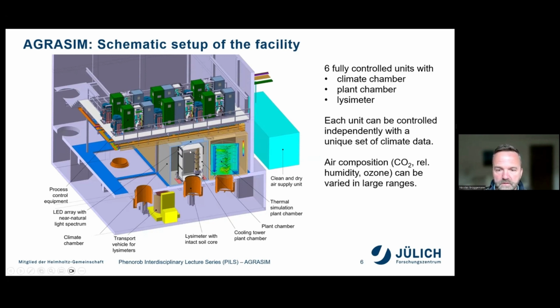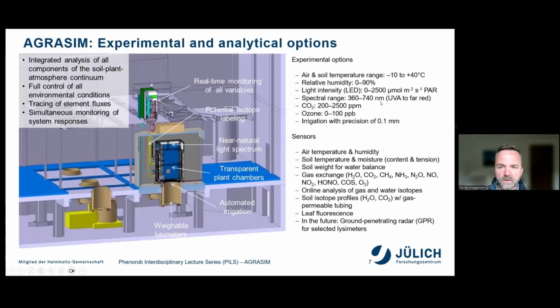And then I will describe these plant chambers in a bit more detail. So we can control each unit independently with a unique set of climate data. So we can run 6 different scenarios if we want. We can vary the air composition with respect to CO2, relative humidity, and ozone in large ranges. So the air and soil temperature range is between -10 to +40 or even beyond. Relative humidity between 0 and 90%. I mean, not 100 because we want to avoid condensation. I will come to that a bit later.